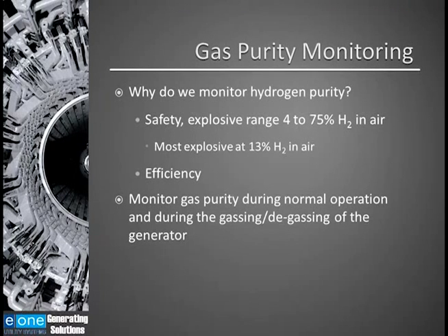You also want to measure the gas purities during the degassing and gassing of the generator, as well as during normal operation of the generator. Risk mitigation could also be added to this list. If you have low purity, you can have problems within the generator. Someone might ask, what is a good hydrogen purity? You want the hydrogen as pure as possible. Typical purity will be better than 96%, sometimes ranging in the area of 98%.